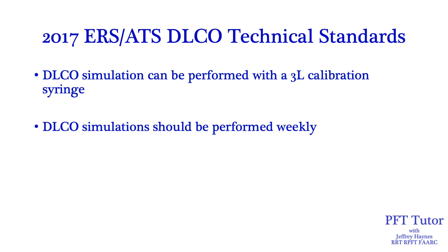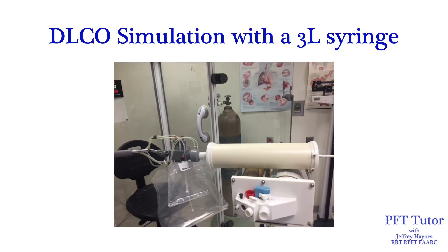It is recommended that DLCO simulations should be performed weekly and as needed when a technical problem is suspected. Performing a DLCO simulation is still somewhat confusing for many technologists, so I'm going to show you how easy and simple it really is.